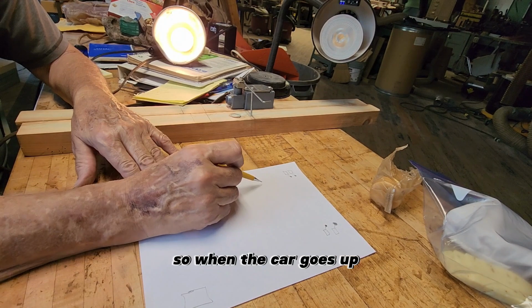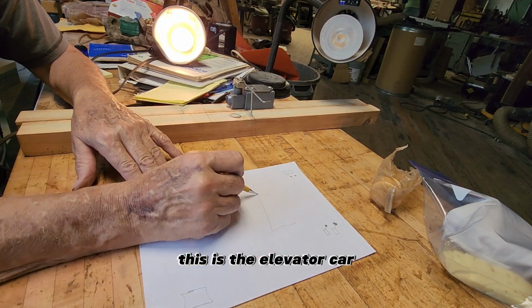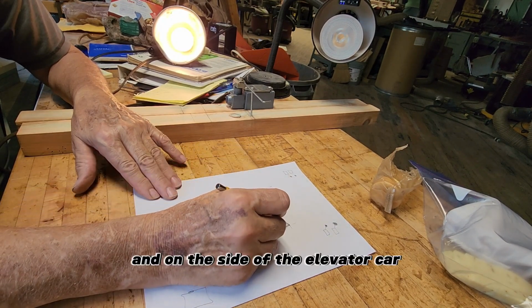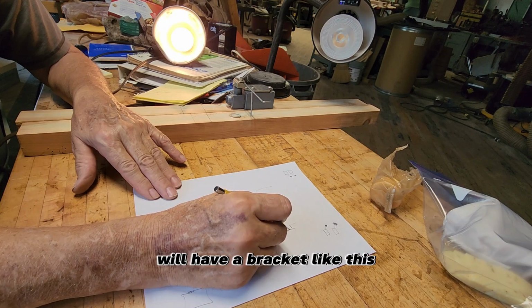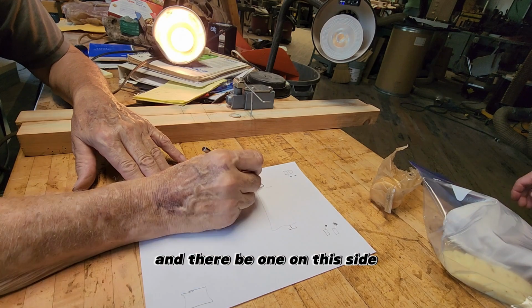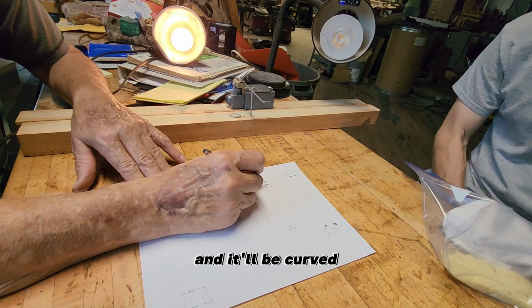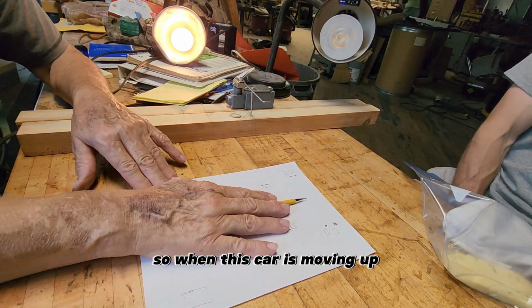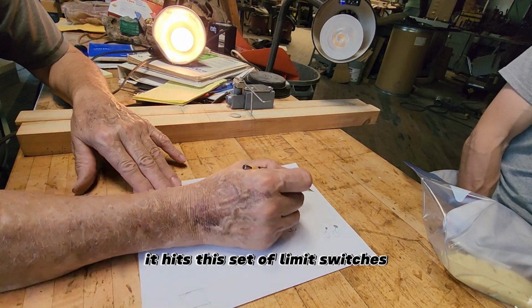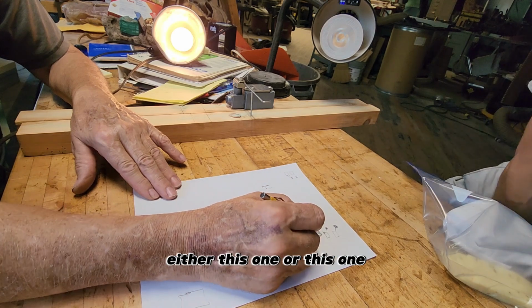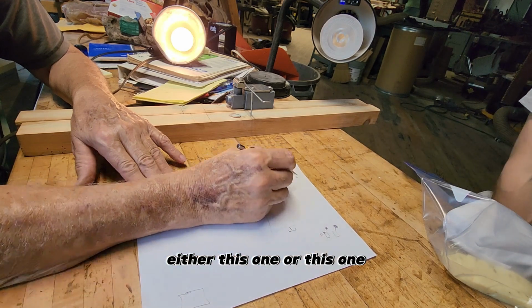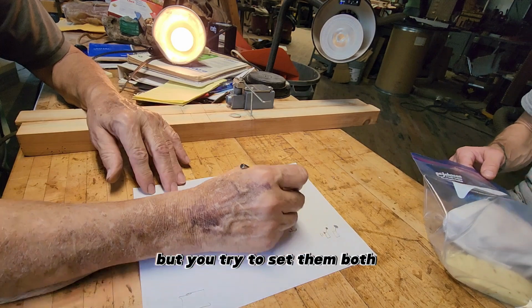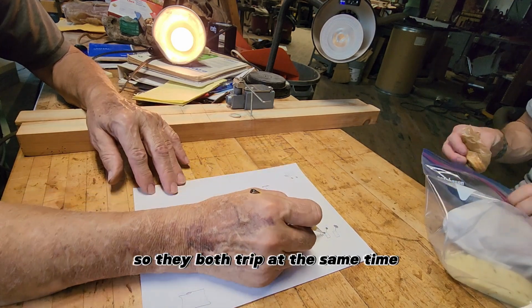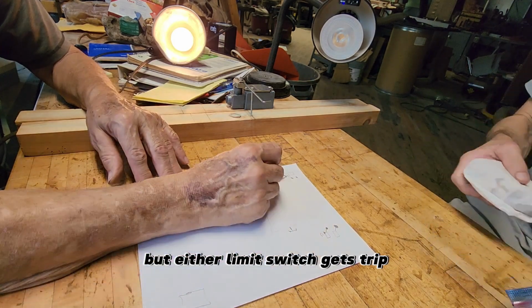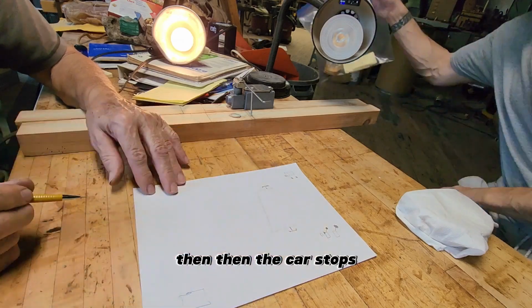So when the car goes up, this is the elevator car. And then on the side of the elevator car, we'll have a bracket like this. It'll be curved. And there'll be one on this side. And it'll be curved. So when this car is moving up, it hits this set of limit switches. If it hits either this switch, or this one, so it's an either or. But you try to set them both so they both trip at the same time. But if either limit switch gets tripped, then the car stops.